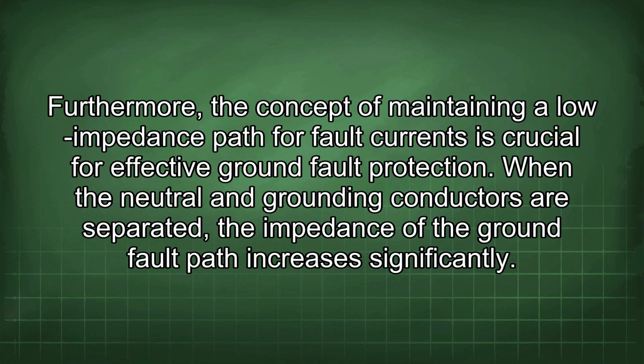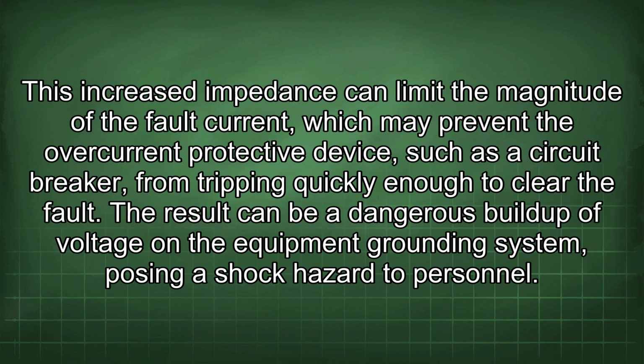Furthermore, the concept of maintaining a low impedance path for fault currents is crucial for effective ground fault protection. When the neutral and grounding conductors are separated, the impedance of the ground fault path increases significantly. This increased impedance can limit the magnitude of the fault current, which may prevent the overcurrent protective device, such as a circuit breaker, from tripping quickly enough to clear the fault. The result can be a dangerous buildup of voltage on the equipment grounding system, posing a shock hazard to personnel.